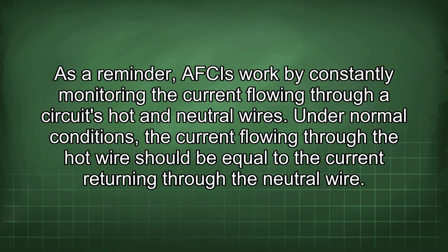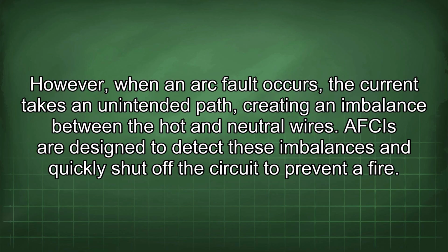As a reminder, AFCIs work by constantly monitoring the current flowing through a circuit's hot and neutral wires. Under normal conditions, the current flowing through the hot wire should be equal to the current returning through the neutral wire. However, when an arc fault occurs, the current takes an unintended path, creating an imbalance between the hot and neutral wires.